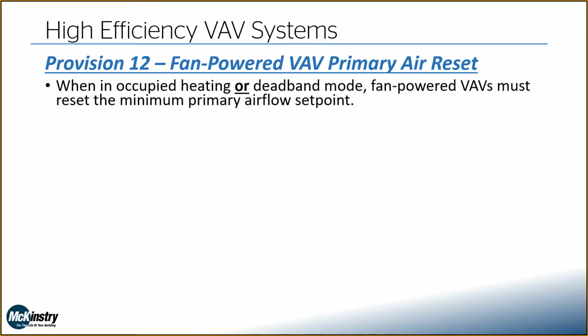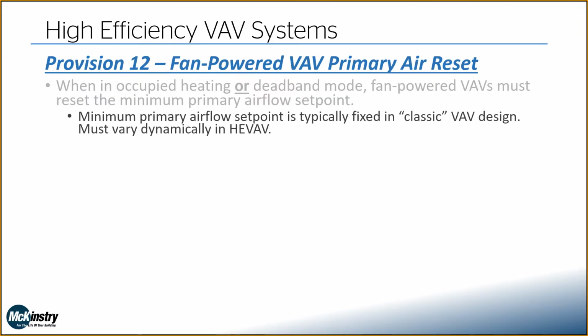Fan-powered VAV primary air reset. This is another one that's a little unusual and might be a little difficult to implement if you're used to standard VAV design. So if you have a fan-powered VAV in occupied heating or in deadband mode, we have to reset the minimum primary airflow set point. So again, talking about classic VAV design, usually that minimum airflow set point is just a fixed value. So maybe it's 100 CFM. We just don't ever allow it to go lower than that 100 CFM minimum set point.